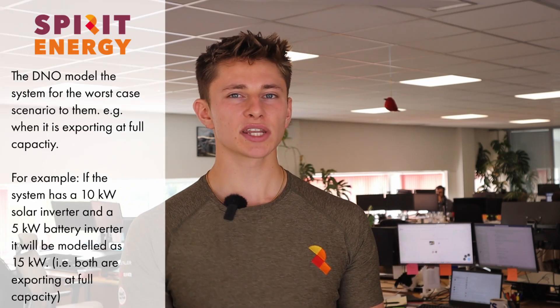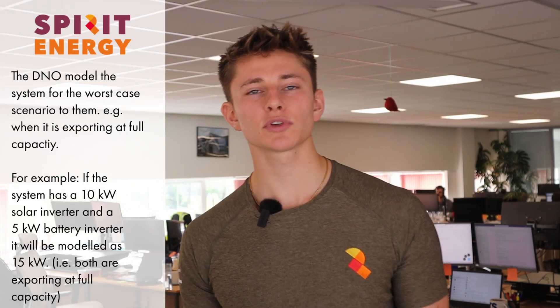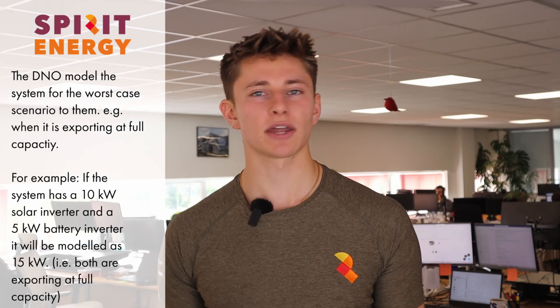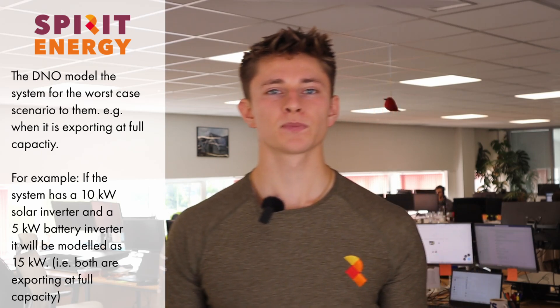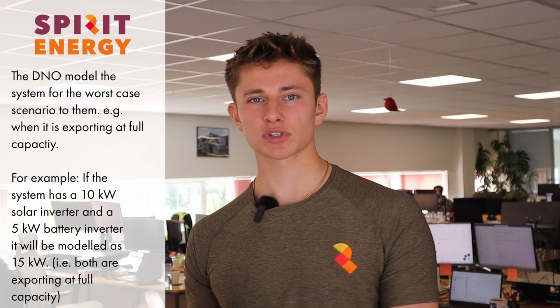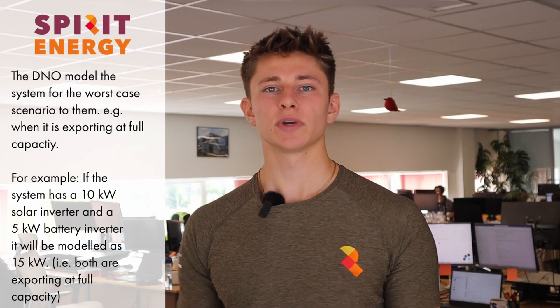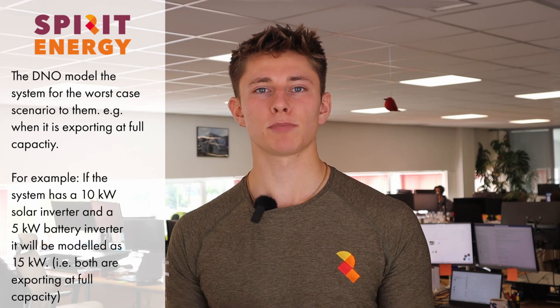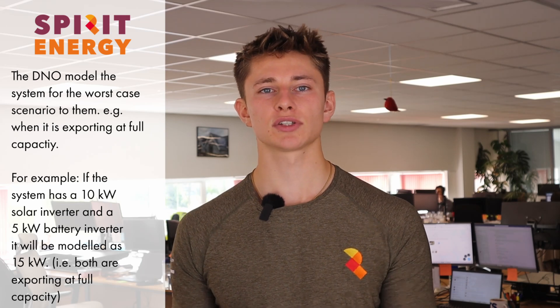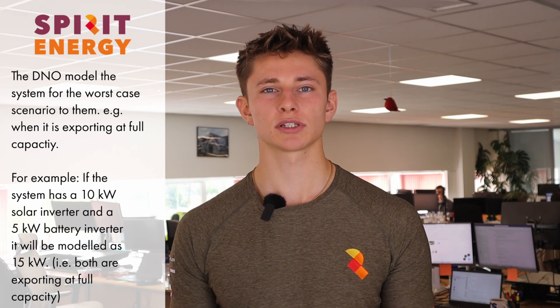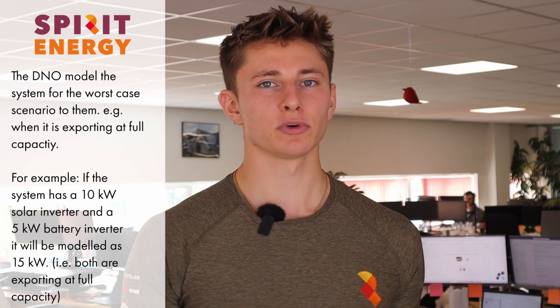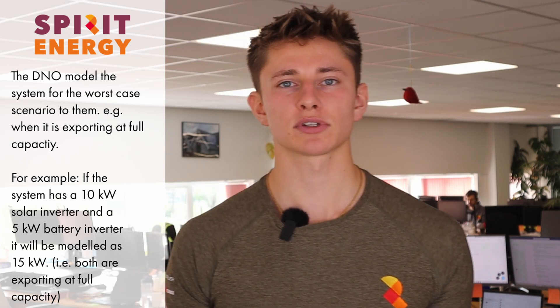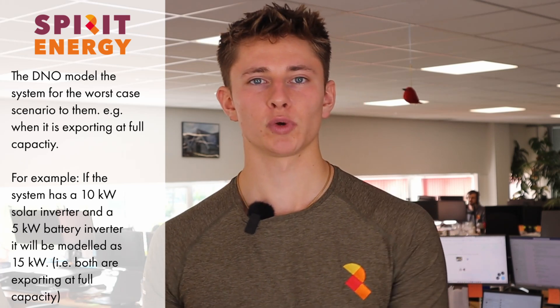For example, if you plan to connect a 10 kilowatt solar inverter and a 5 kilowatt battery inverter, they will model for the most impactful scenario, which is when both inverters are exporting to the grid at maximum capacity — i.e. 15 kilowatts being pushed out to the grid through your local electricity supply.